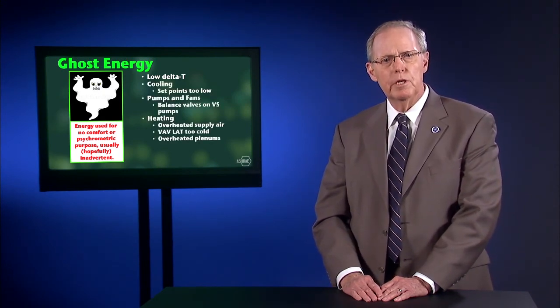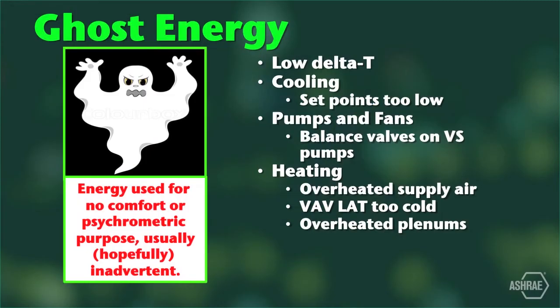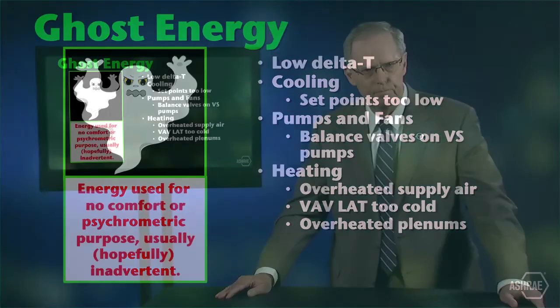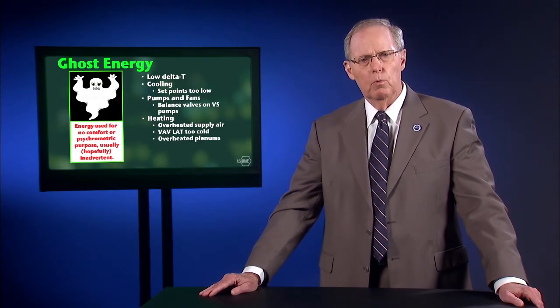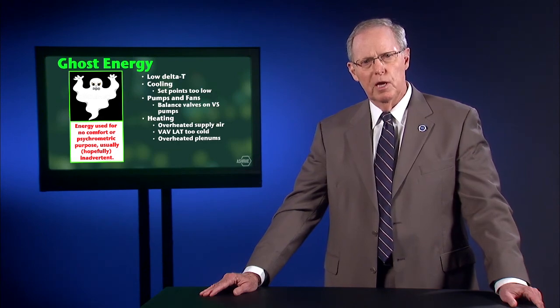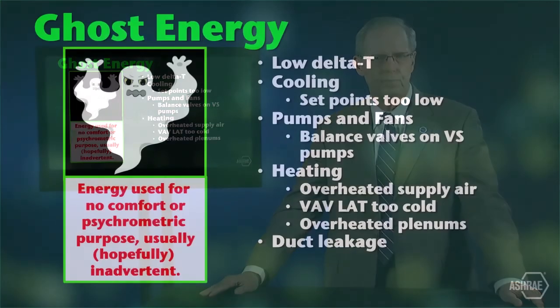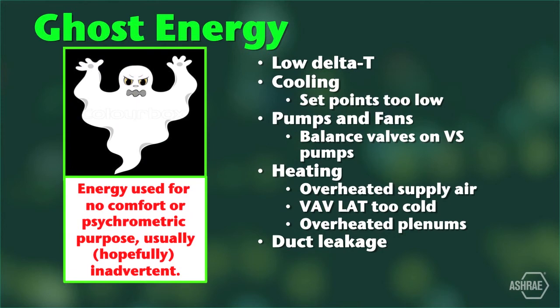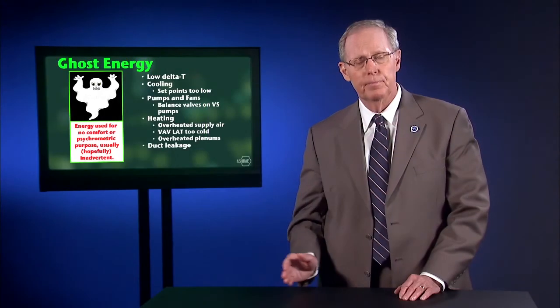Now, a common winter ghost is raising the supply air temperature to address cool rooms. That usually does an excellent job of heating the ceiling and a marginal job of solving the problem. There's an excellent article about warm air stratification in the November 2017 ASHRAE Journal. Duct leakage. When the return air is 3 degrees colder than the coldest room? I found 20% duct leakage on a new project after it had been commissioned.